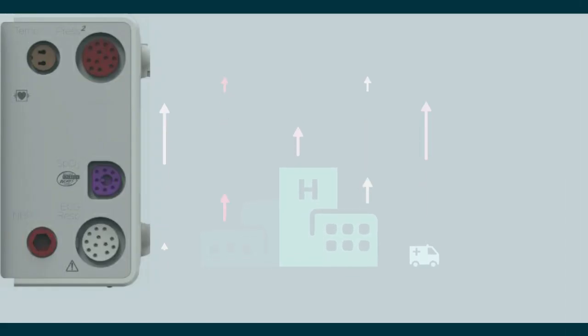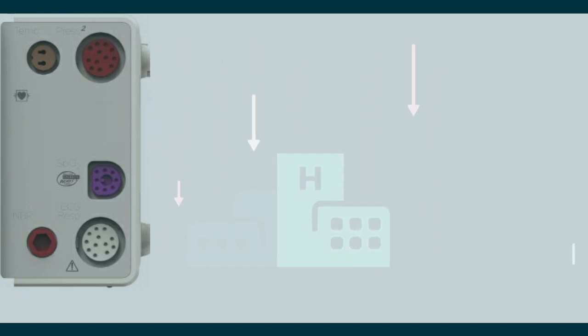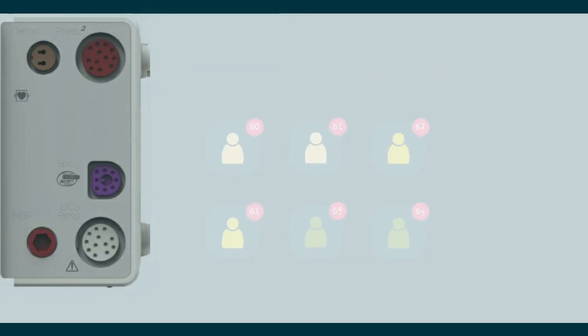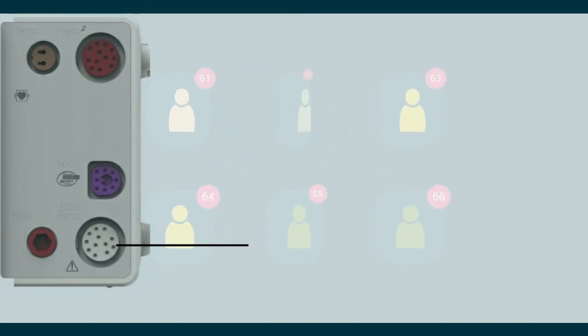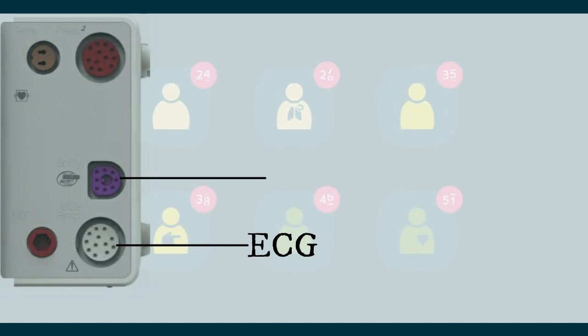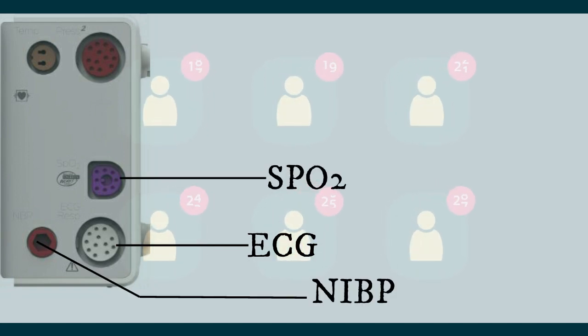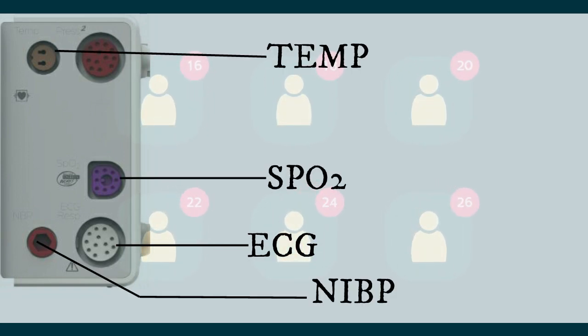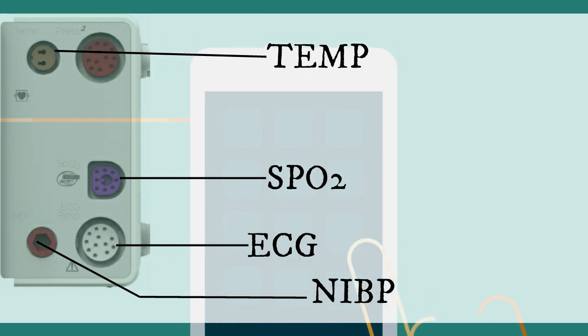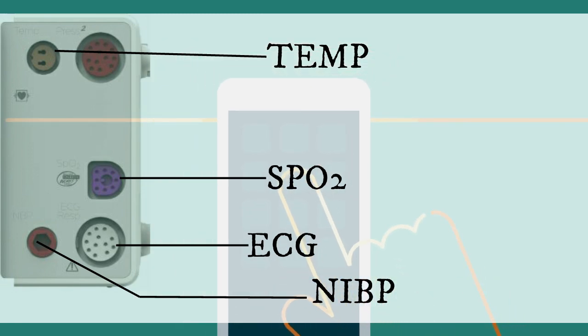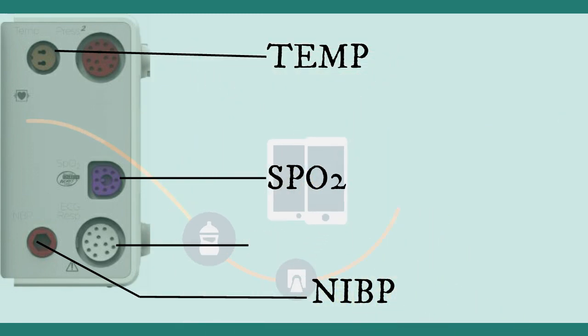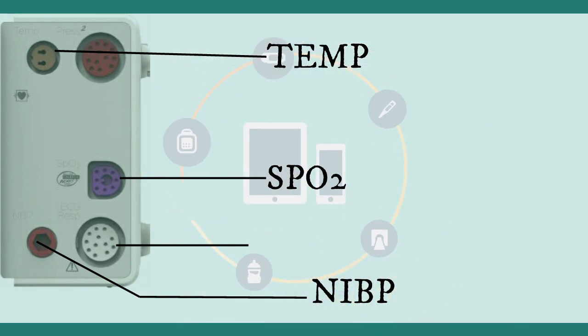Let's begin with basic vital sign monitors. This type of monitor consists of ECG, SPO2, NIBP, and temperature. Basically, this type of monitor is used in day case and outpatient departments in the hospital.